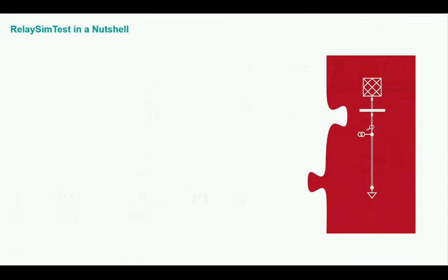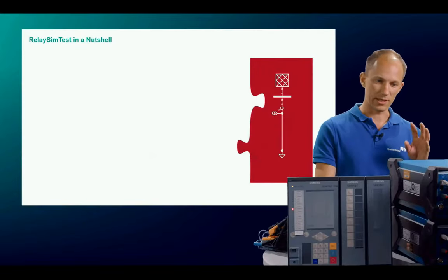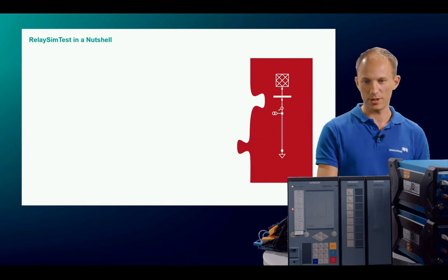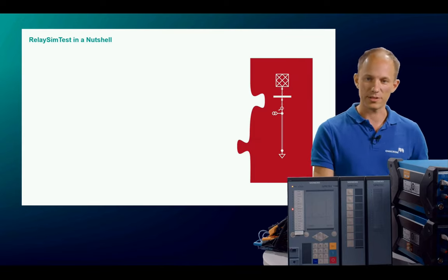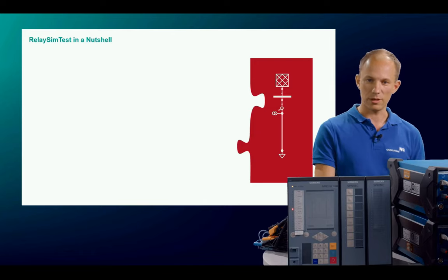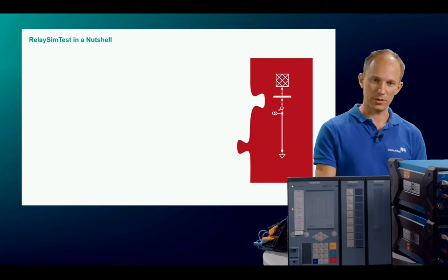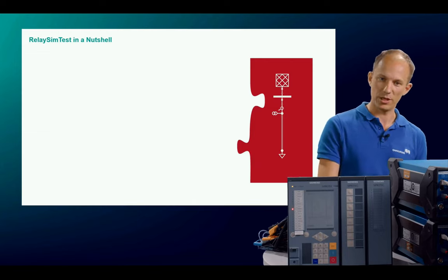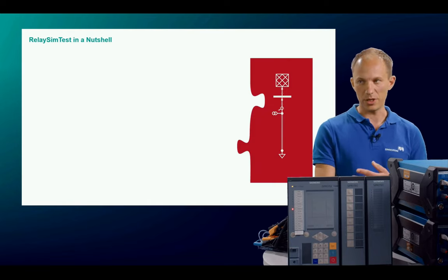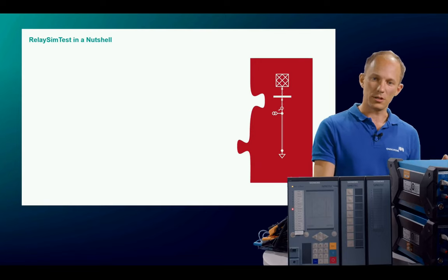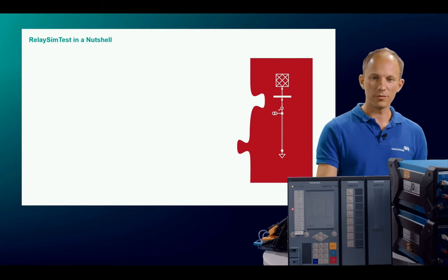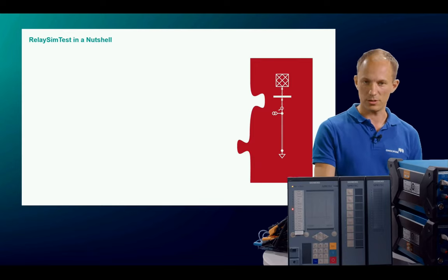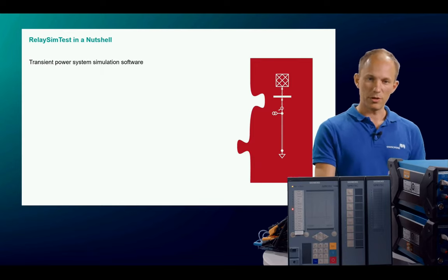So what is Relay SimTest in a nutshell? You see the focus there is not on the single relay, but on the power grid. You see that on the right-hand part of the slide with the infeed, the busbar, a line, and a load. So we really simulate the components of an electrical power grid, and then we simulate events on that power grid. That could be a fault incident. It could be that the load is changing, or the infeed is changing. There could be other events, a circuit breaker opens or closes or even fails. So Relay SimTest is first of all a transient power system simulation software.